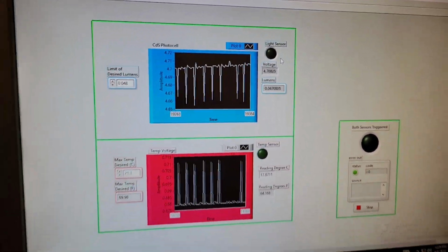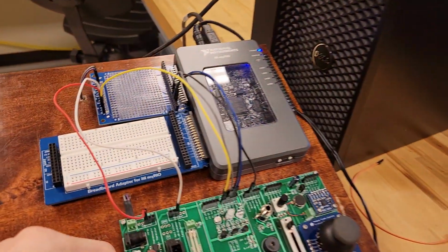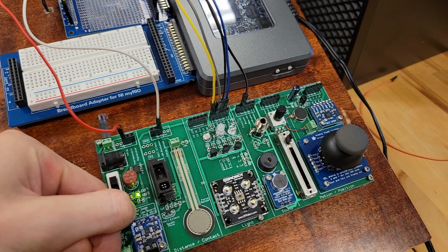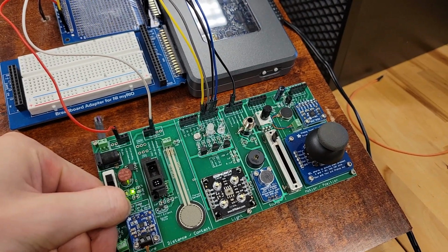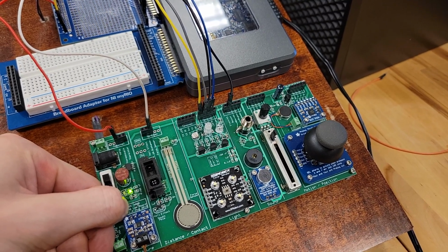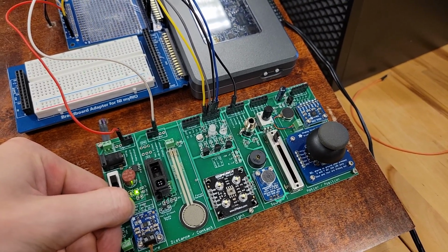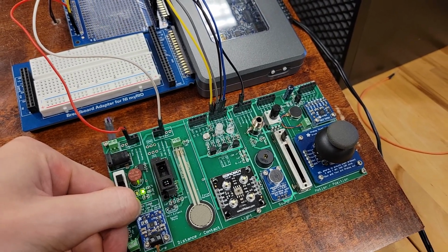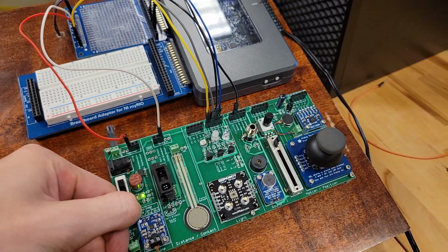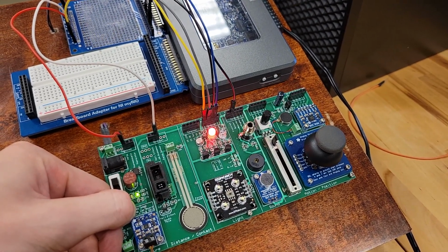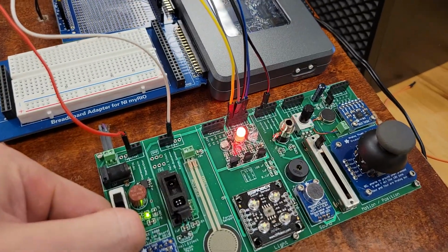We're going to go ahead and test this real quick. We're going to test the temperature sensor first. So I'm going to pinch down on it, and it should respond to my hand. There's an on delay timer on the temperature sensor that we'll review here in a moment. But once it meets the condition, it has to wait 5 seconds of continuous true condition, and then it will actually turn on the pump from the temperature change. This is to avoid any kind of flickering effect that we were getting before, where it was sitting on the threshold and it would kind of just flicker. But you see there, it's not flickering, the motor's on.